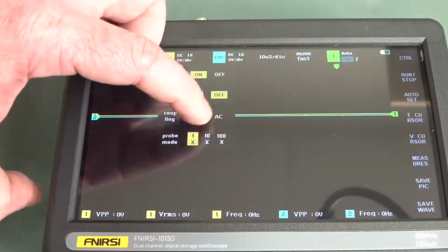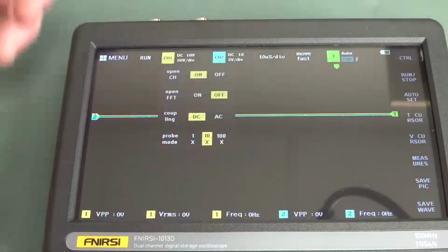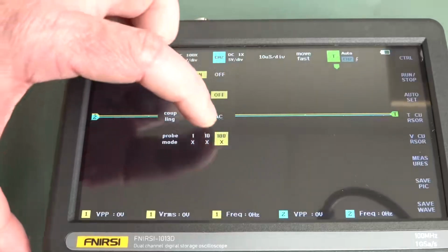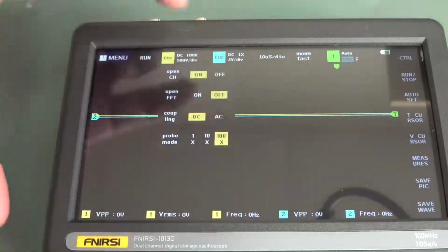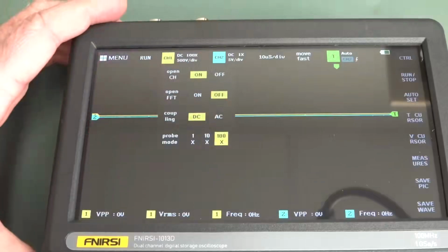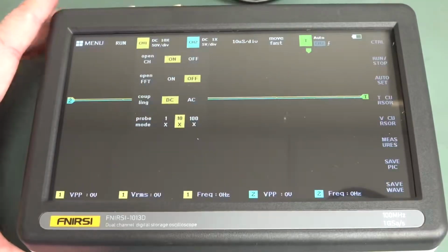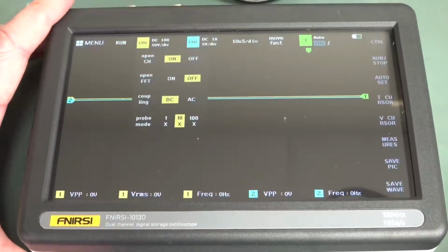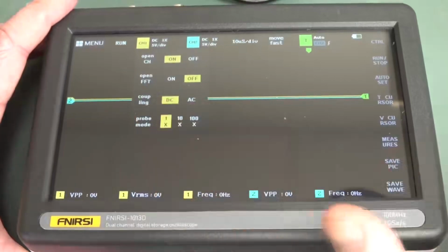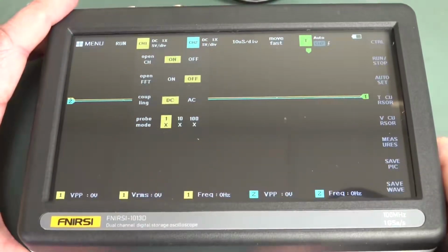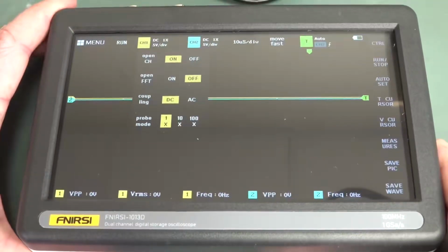Okay, well, nothing popped up. Coupling, AC or DC coupling, and the probe mode ×1, ×10, or ×100. So that's handy if you did have an external ×100 high voltage probe. With 50 millivolts per division minimum on ×1, you're not going to be able to get really low level stuff on this.